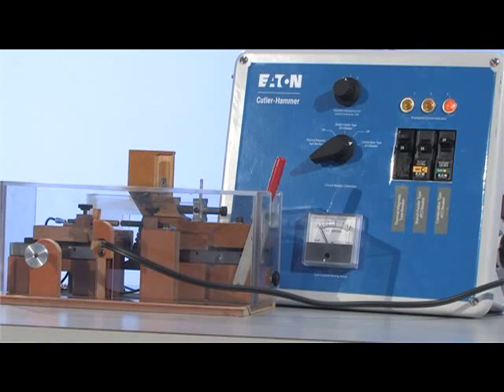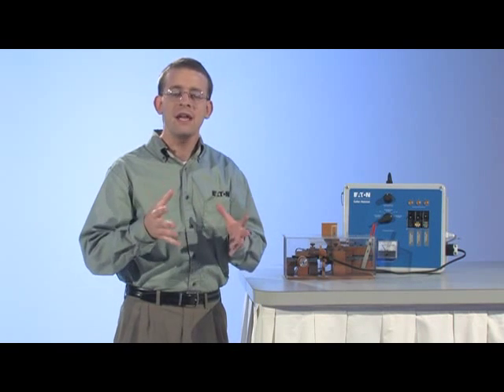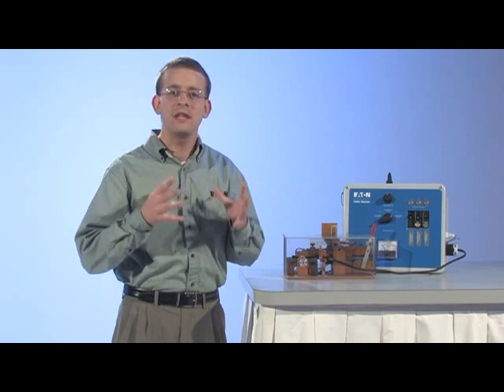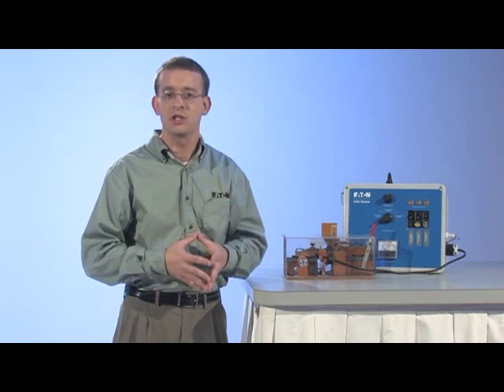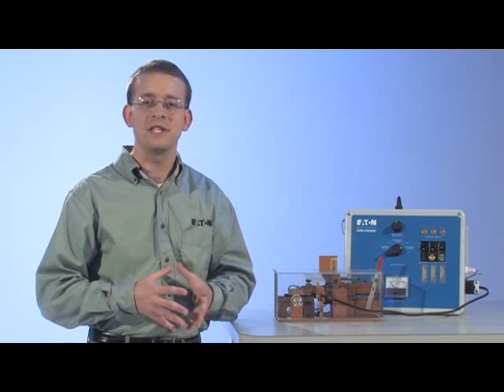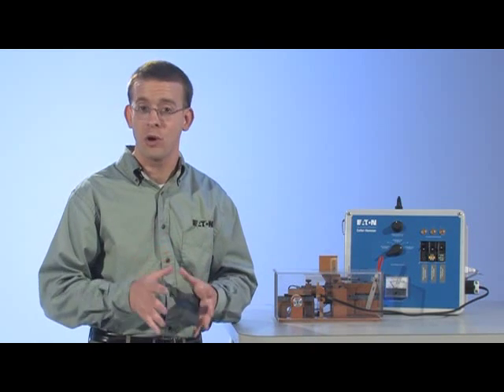The challenge with designing the combo AFCI breaker is that every electrical device will create arcs during their operation. When the contacts close or separate, they create these small arcs, just as I was demonstrating in the demo here. The protective device needs to differentiate between these operational or intentional arcs, such as the flipping of a light switch or operation of a motor, and the non-operational or dangerous arc. The combo AFCI breaker is designed to ride through these operational arcs and only look for sustained low current arcing before tripping.